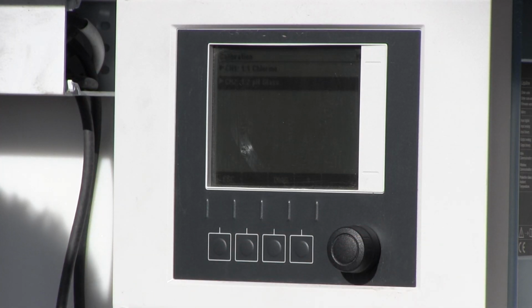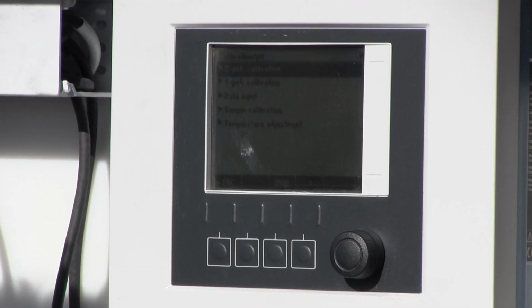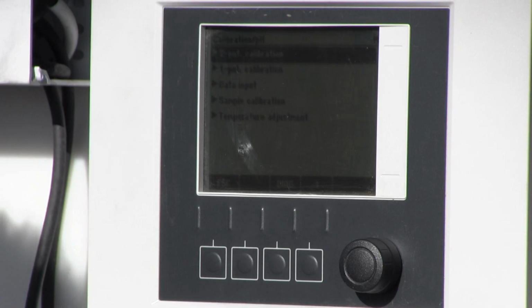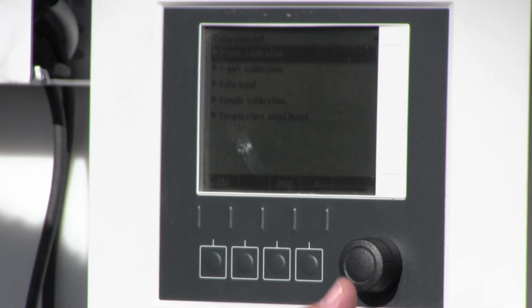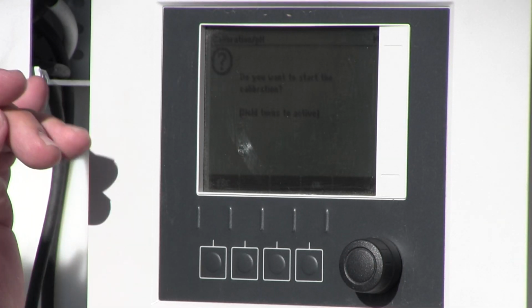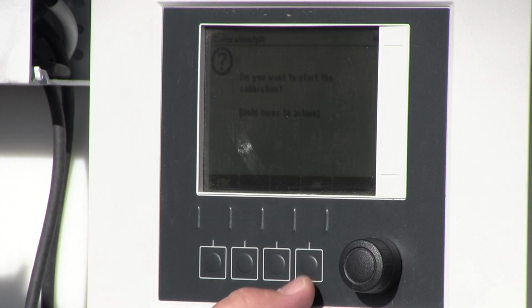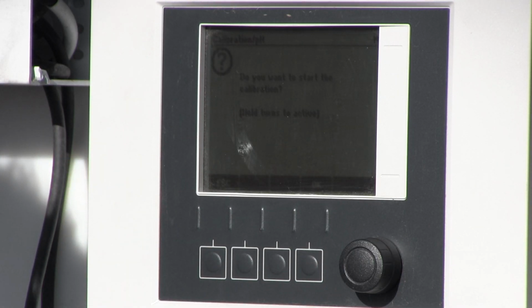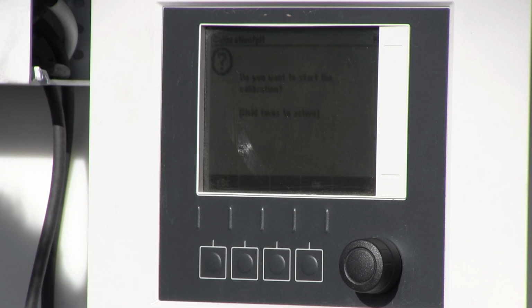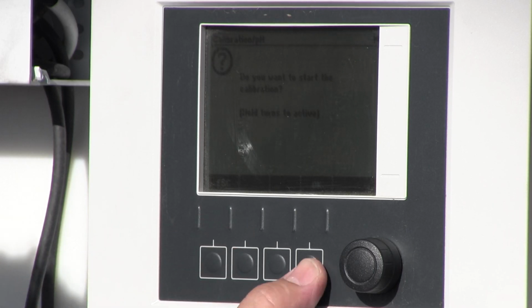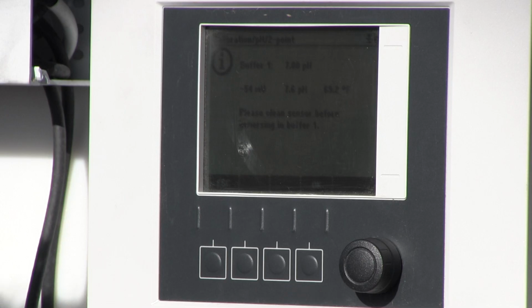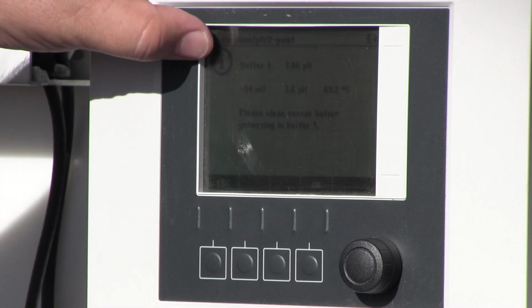I will use the jog shuttle button to roll over to pH and highlight it. I'll hit enter and select 2-point calibration. That's the very top option. It says, do you want to start the calibration? Hold turns to active. Again, this means that 4 to 20 milliamp output that's currently being sent off will clamp into place. We select OK. It gives us some information.